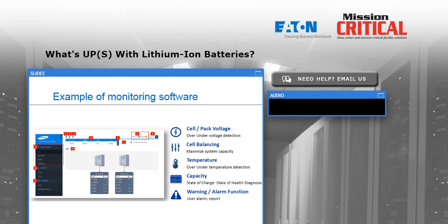The battery management system monitors the voltage of the battery at the cell level and the pack level. It performs balancing to make sure all the batteries are balanced within about a tenth of a volt, which is one of the ways we eliminate the possibility of over-temperature conditions. We monitor temperature, state of charge, and state of health, and provide alarm information both to the UPS so it can annunciate an alarm, and also independently over a network, maybe a Modbus network used in a typical data center facility.